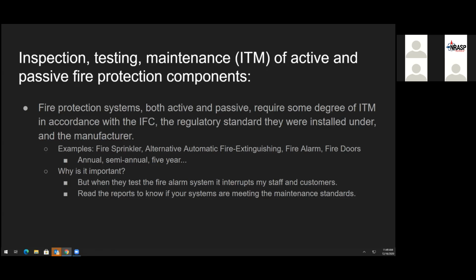Some of you may have fire pumps in your facilities. Many fire pump manufacturers require weekly testing of that fire pump. Now, it may be a very cursory test, but just make sure that you're testing all of your systems, not only to the code and to the standard, but to the manufacturer as well.